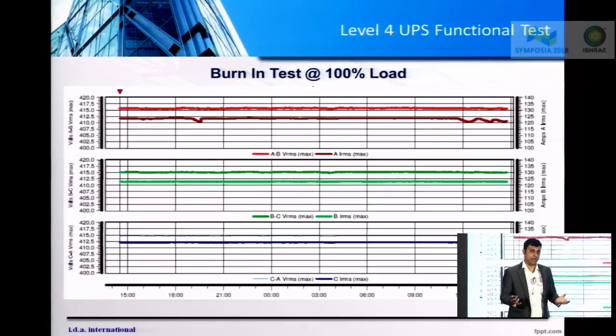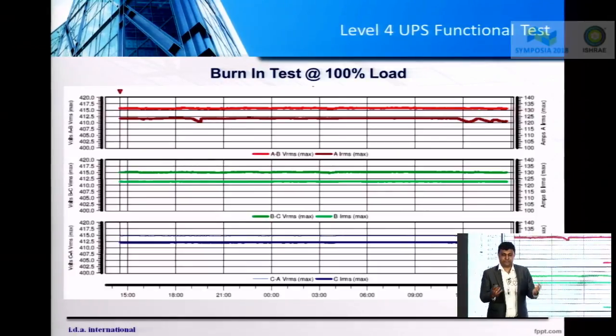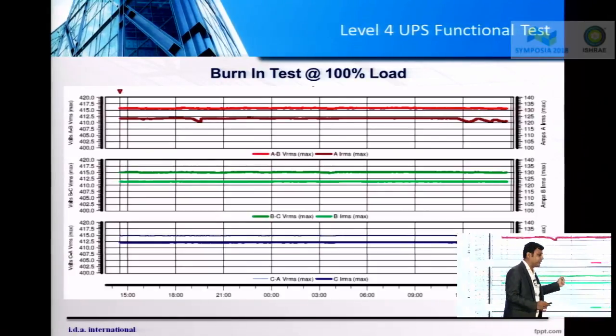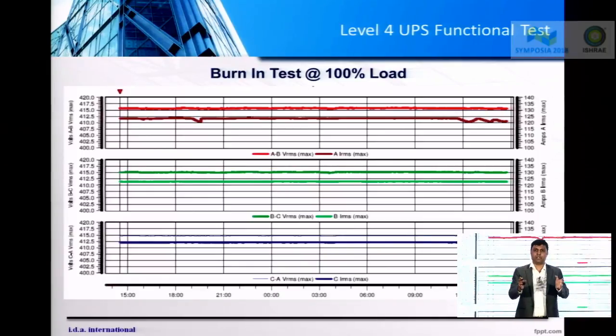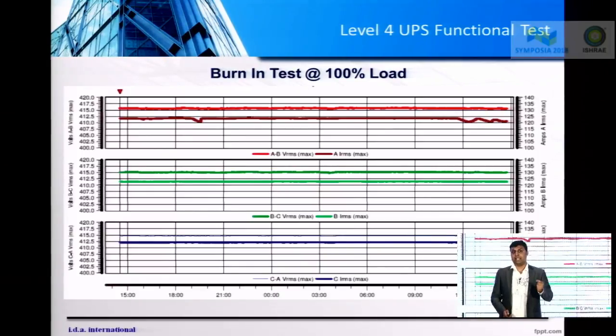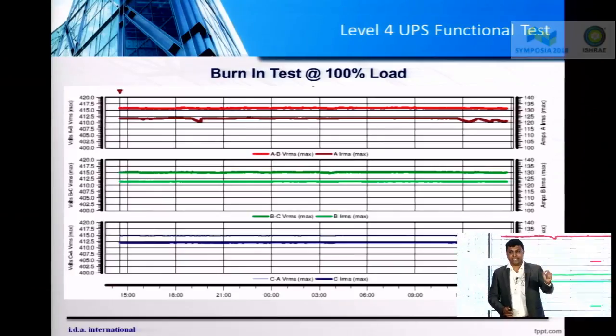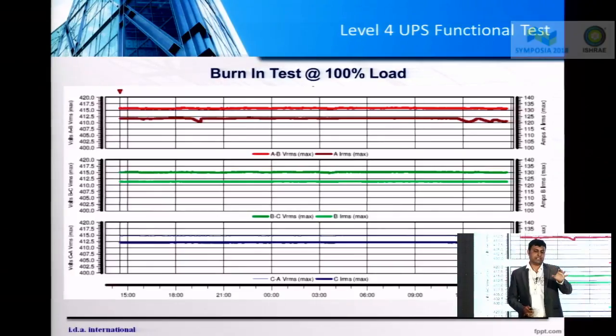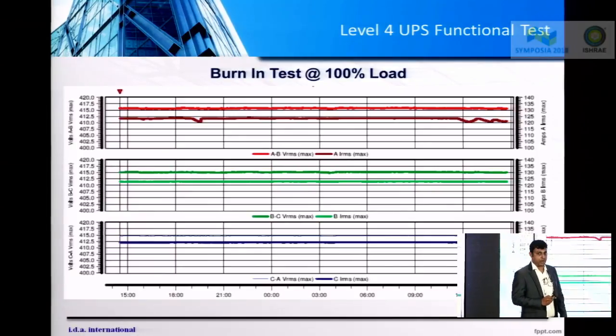I mean, I don't claim it, but we have seen it in the past, that during the burn-in test, when you load a particular equipment to its maximum loading condition, there are chances that there could be a weak link which could result in a failure. So burn-in test becomes a very important part of a UPS performance verification.